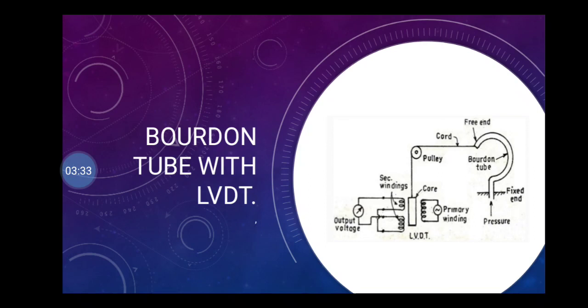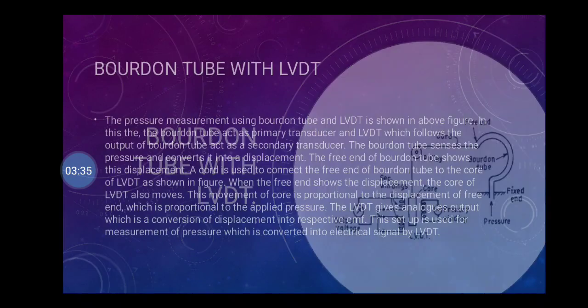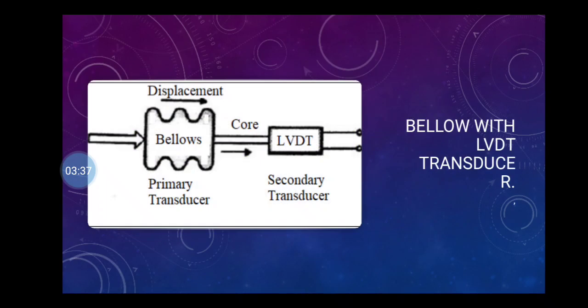Now, bellow with LVDT transducer. It's used to measure pressure. LVDT is a linear variable differential transformer. It works on the transformer action: when the primary is supplied with AC, the EMF, that is the voltage, is induced in the secondary.